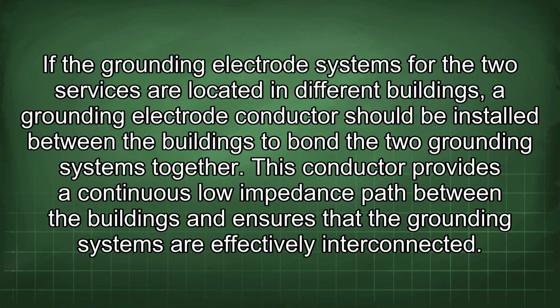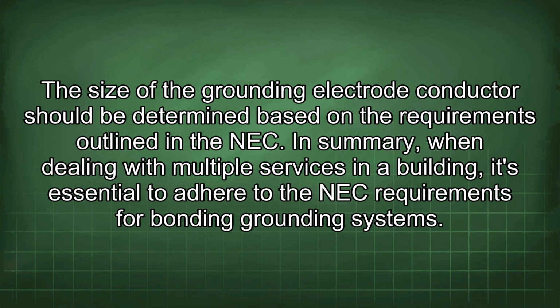If the grounding electrode systems for the two services are located in different buildings, a grounding electrode conductor should be installed between the buildings to bond the two grounding systems together. This conductor provides a continuous low impedance path between the buildings and ensures that the grounding systems are effectively interconnected. The size of the grounding electrode conductor should be determined based on the requirements outlined in the NEC.